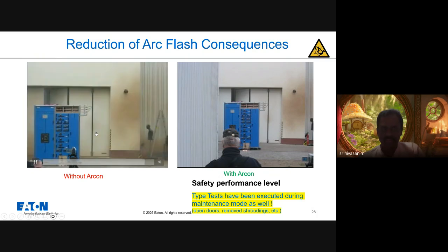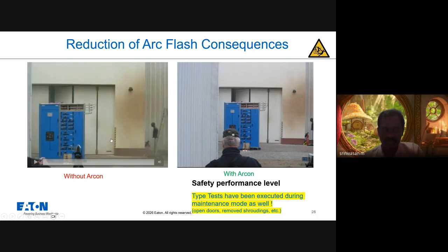You could see the fumes and gas coming out of the switchgear. If the Arcon is not installed in the switchboard, you might have noticed that we put a dummy like a human being at an approximate distance of 7 to 8 meters. The fumes and gases emanating from the switchgear reach the human being, even at the farthest distance of 7 or 8 meters.